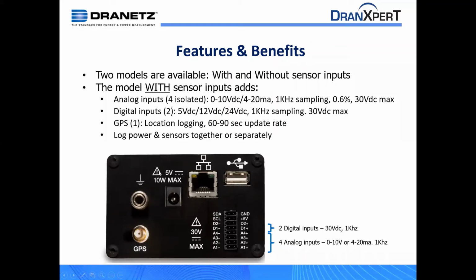The model with, and you can see on the back panel here, has 4 analog inputs available, and those are each individual input. They're 4 isolated. Each can be configured for a 0 to 10 volt DC input or a 4 to 20 milliamp DC input, and all the 4 can be set up differently. There is a 1 kilohertz sampling rate for that. In addition, you have available 2 digital inputs that you can see over here. And there are 5 or 12 or 24 volts DC, and again, they are sampled in parallel at that 1 kilohertz rate.